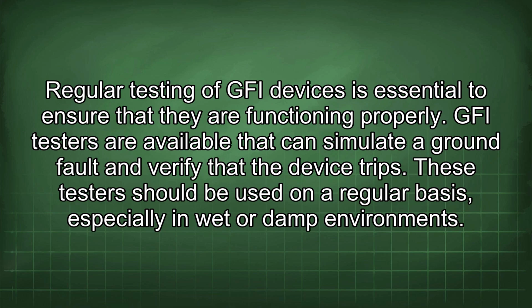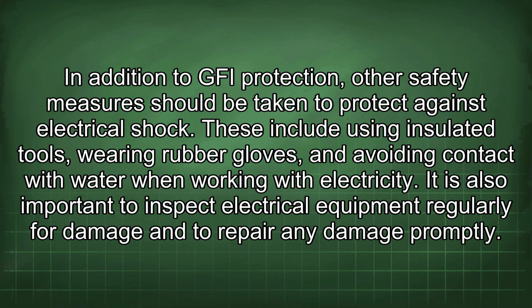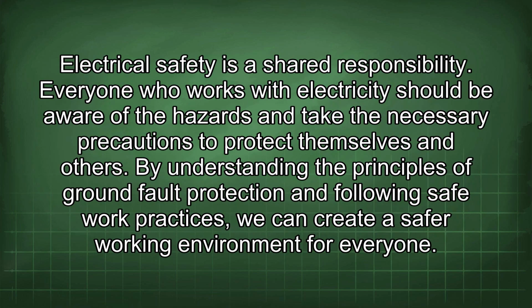Regular testing of GFI devices is essential to ensure that they are functioning properly. GFI testers are available that can simulate a ground fault and verify that the device trips. These testers should be used on a regular basis, especially in wet or damp environments. In addition to GFI protection, other safety measures should be taken to protect against electrical shock. These include using insulated tools, wearing rubber gloves, and avoiding contact with water when working with electricity. It is also important to inspect electrical equipment regularly for damage and to repair any damage promptly. Electrical safety is a shared responsibility. Everyone who works with electricity should be aware of the hazards and take the necessary precautions to protect themselves and others. By understanding the principles of ground fault protection and following safe work practices, we can create a safer working environment for everyone.